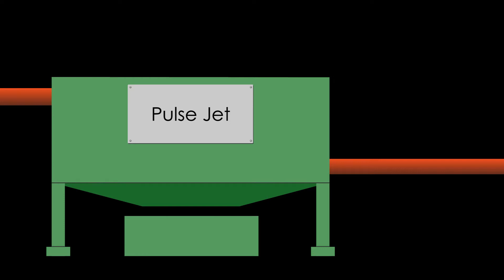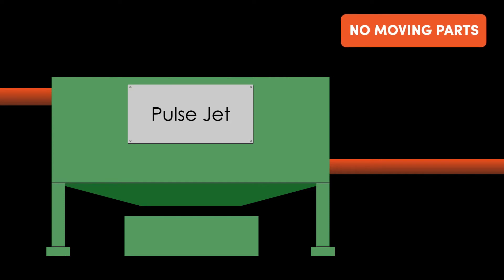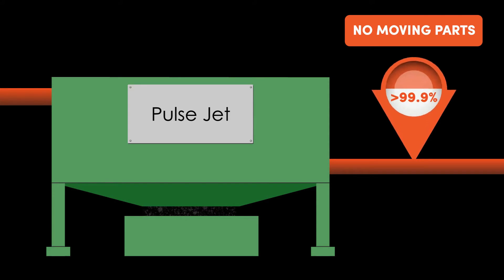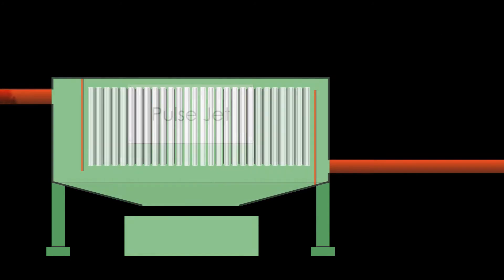These industry workhorses boast no moving parts in their basic configurations and allow collection efficiencies greater than 99.9%. In the PulseJet dust collector, the dusty airstream usually enters from below the bags or filters and is pulled upwards through the filters, where dust is captured on the exterior surface and clean gas passes through to the clean air plenum side or exhaust.